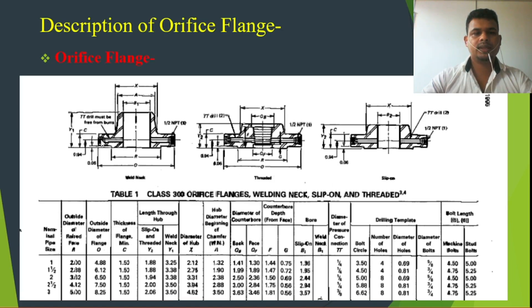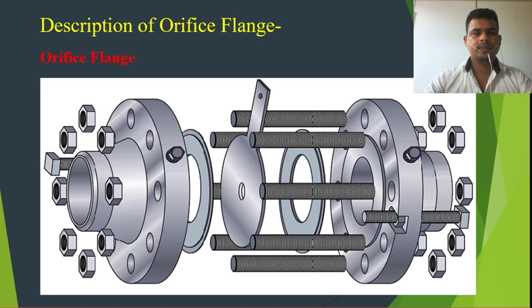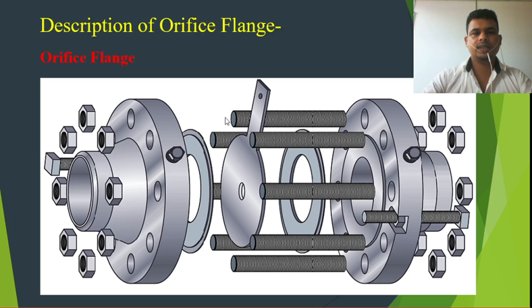For the tap holes, threading, and jack screws, all the standards we follow are from ASME B16.36. You can see in this figure an orifice flange union — two orifice flanges with the orifice plate in between. We need two gaskets inside. You can also see the jack screw here. This is one example of an orifice flange connection.